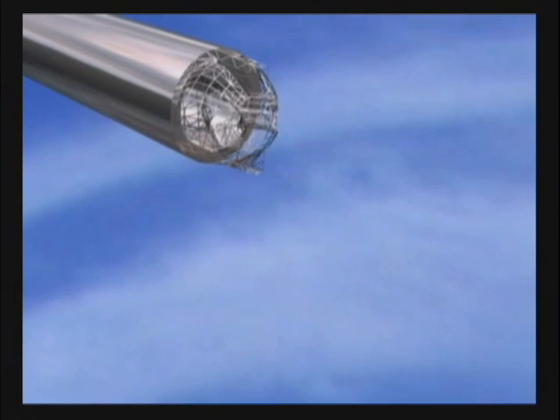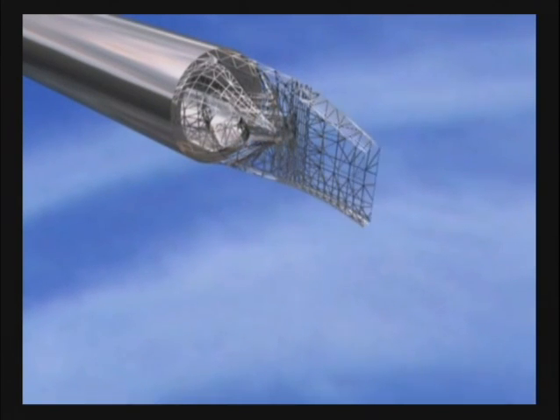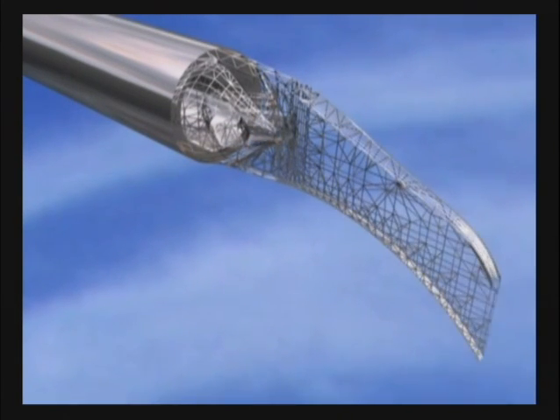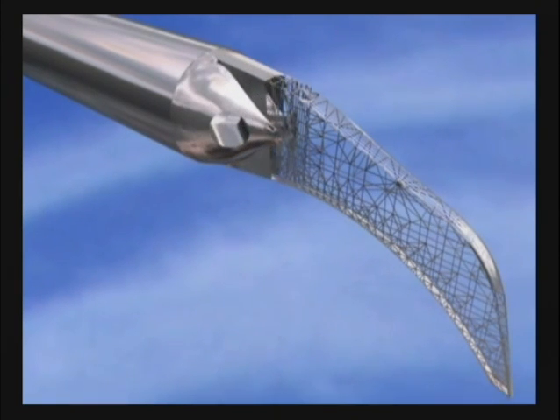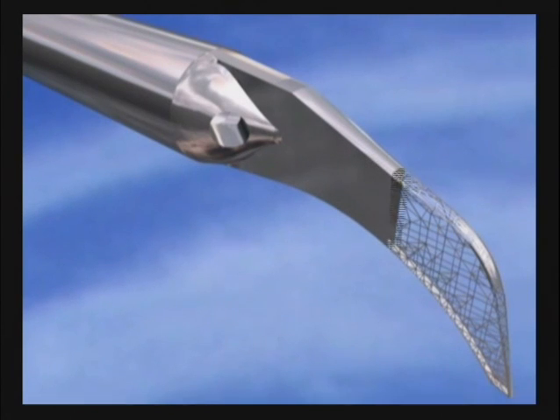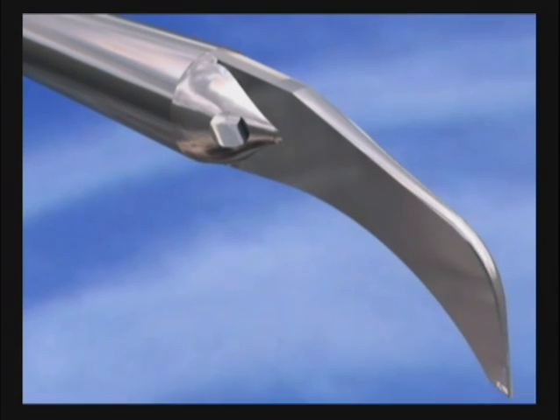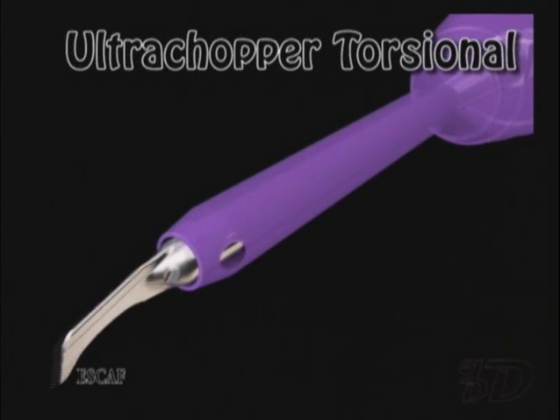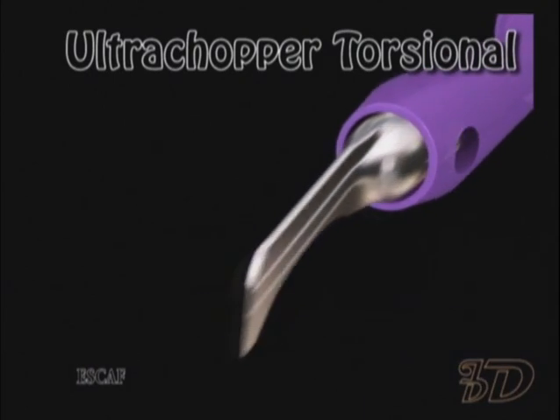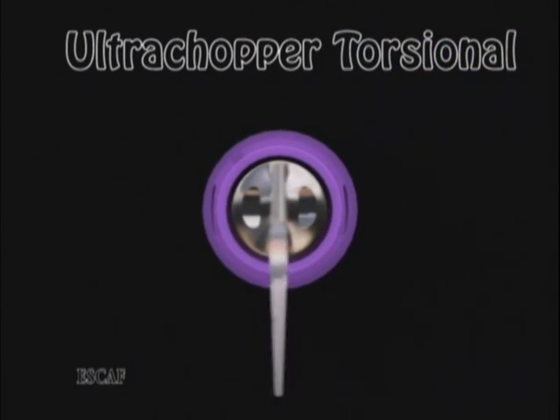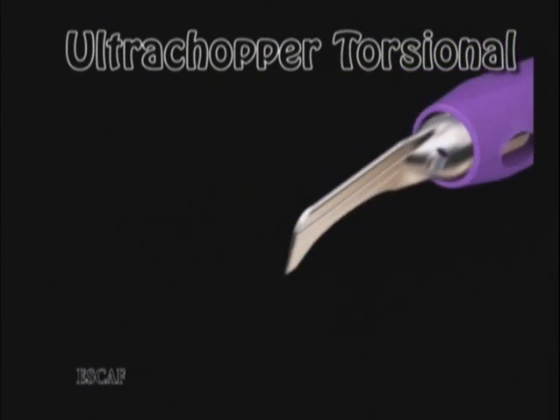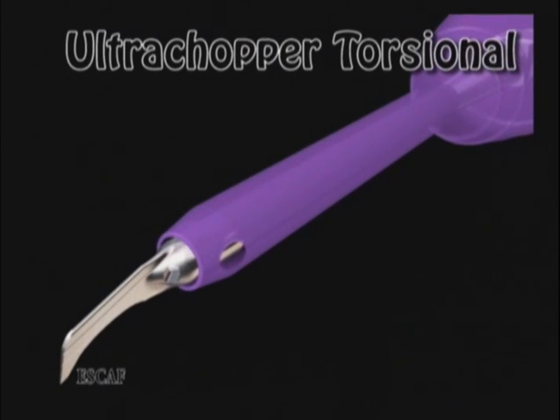It is the phacoemulsification needle flattened on its tip, angulated with a downward bend, thinner in the inferior portion, internally hollowed with two aspiration pores placed laterally. It is attached to the phacoemulsification handpiece and therefore it generates ultrasonic vibrations in position 3 of the foot pedal, behaving like a true ultrasonic knife.